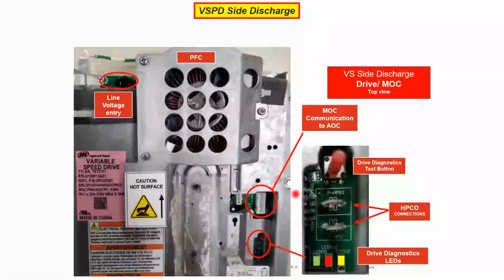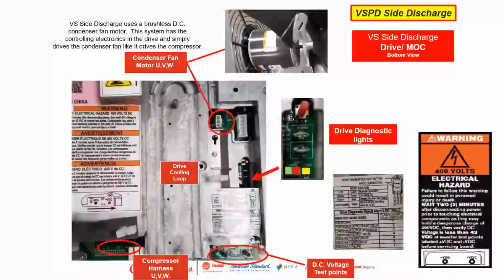Here's a closer look at those pins. Here's our MOC to AOC harness. Drive diagnostic LEDs. Again, I don't usually use those much because the AOC is going to display them for me, or the thermostat. Again, here's that data plate for the variable speed drive. We're going to need that if we're doing a drive replacement. Condenser fan motor is 3-phase. Here's our drive cooling loop.